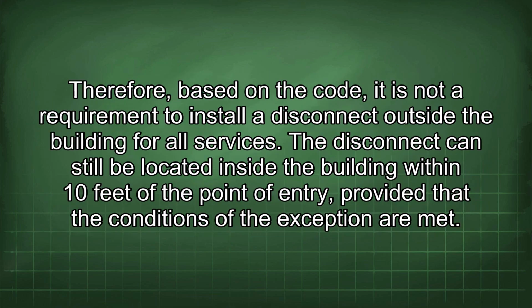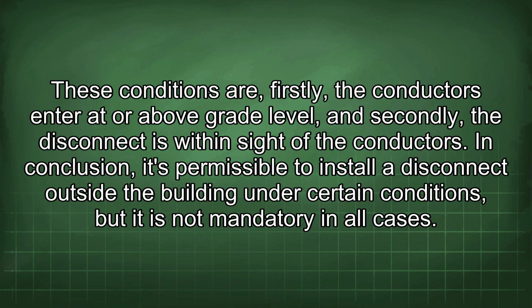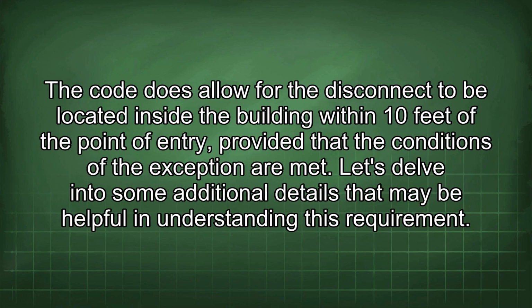Therefore, based on the code, it is not a requirement to install a disconnect outside the building for all services. The disconnect can still be located inside the building within 10 feet of the point of entry, provided that the conditions of the exception are met. These conditions are, firstly, the conductors enter at or above grade level, and secondly, the disconnect is within sight of the conductors. In conclusion, it's permissible to install a disconnect outside the building under certain conditions, but it is not mandatory in all cases. The code does allow for the disconnect to be located inside the building within 10 feet of the point of entry, provided that the conditions of the exception are met.